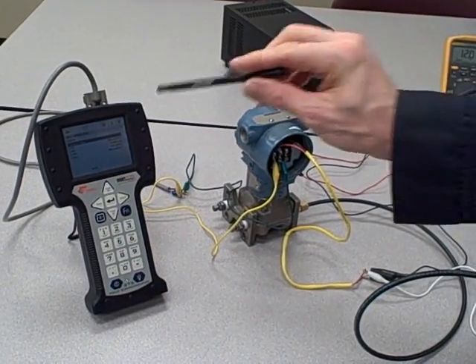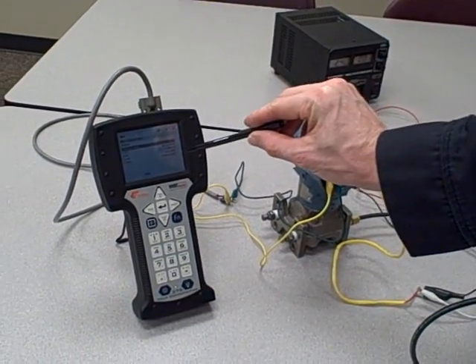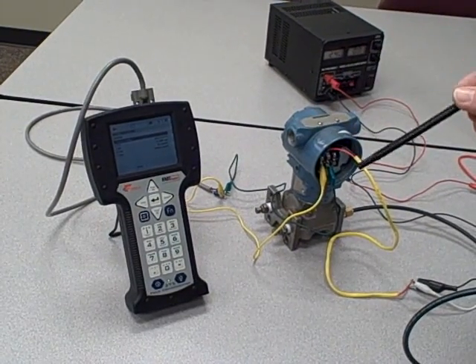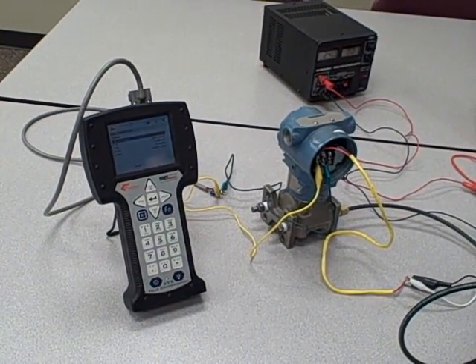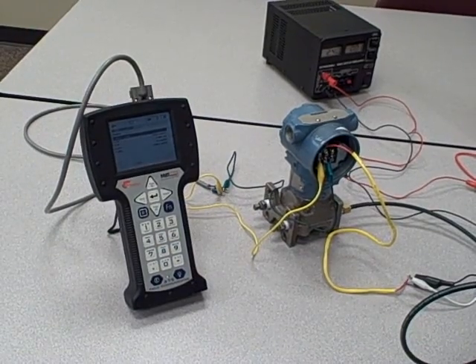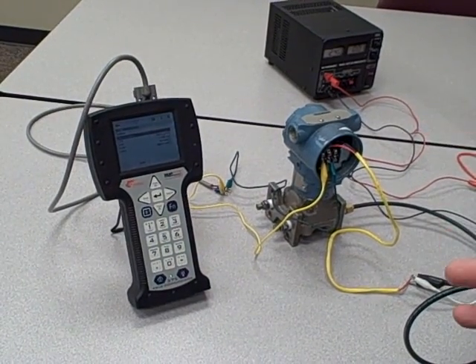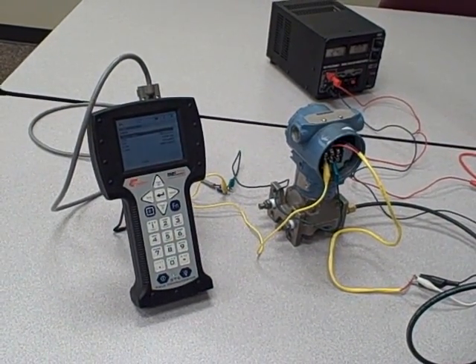So using this technology, we can interrogate the transmitter using a computer. We can take a look at its range values, change the range values, change parameters such as damping and linearization, perform calibrations, assign tag numbers, all kinds of stuff we could never do in the analog world.